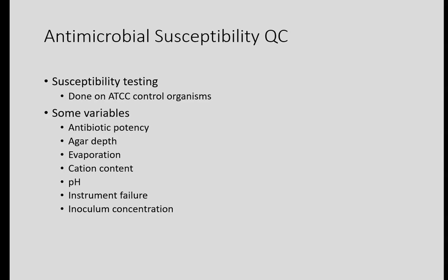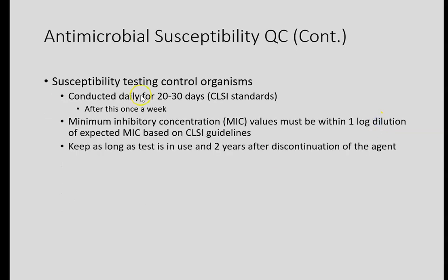The antibiotics have to be handled properly — they haven't been left to sit out on the table at room temperature for two weeks and then you try to run QC on them, because that's probably not going to work. We're checking to see if the instrument is actually doing what it's supposed to be doing, whether it's an inoculator or an instrument that is actually reading the plate.